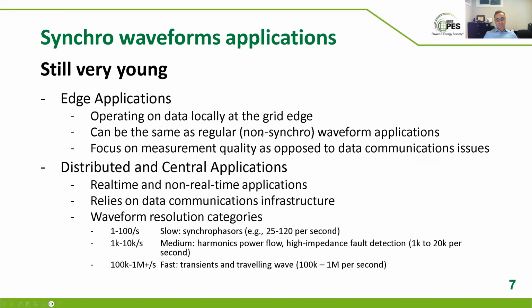Let me move on. We'll talk a bit about that because one of the emphases here is that if you do have a deep data sensor in the modernized grid, with the changes we are seeing in our grid, with all the renewables, that is a much more practical investment, because you can use that sensor or that measurement for many, many applications. Often enough, the cost of the crew going to the field to put in a sensor is much higher than the cost of the equipment itself. So it's really important not to need five different types of sensors for five different applications. It would be great to have one set of sensors installed and use them for those five different applications.